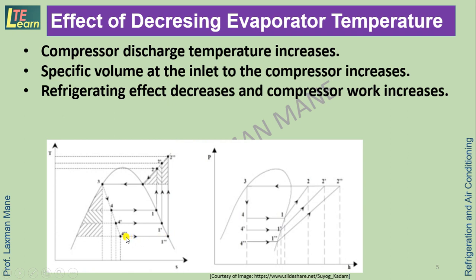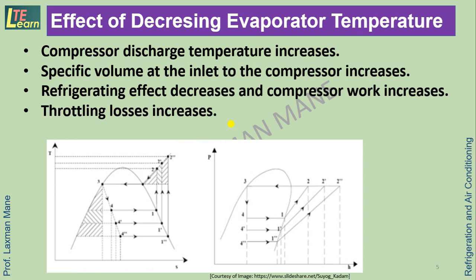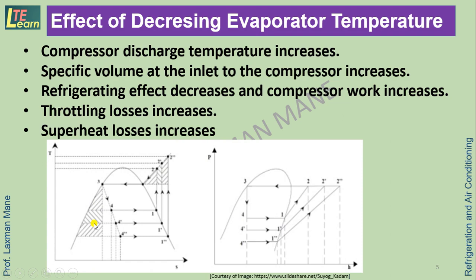The refrigerating effect decreases — the enthalpy difference across the evaporator decreases — while compressor work, shown by the enthalpy difference from point 1 double-dash to 2 double-dash, increases. This ultimately reduces the COP (coefficient of performance). Additionally, throttling losses and superheat losses increase, as shown by the hatching on the PH diagram.